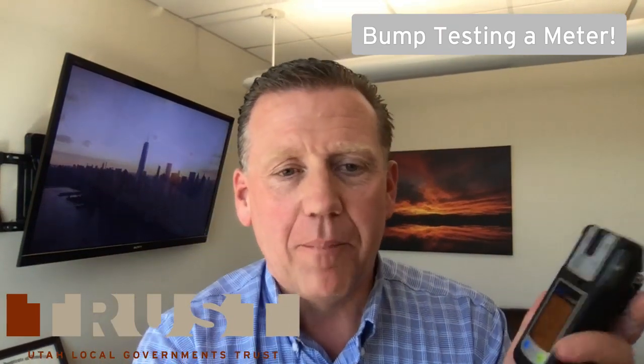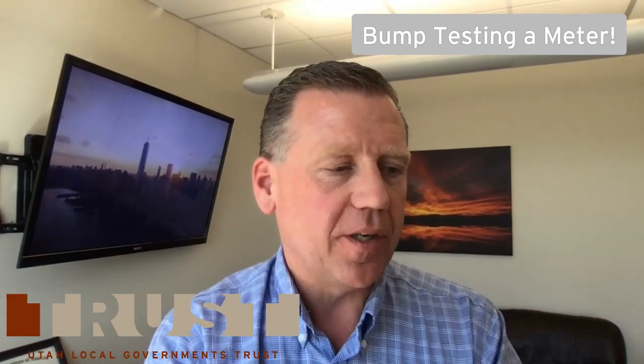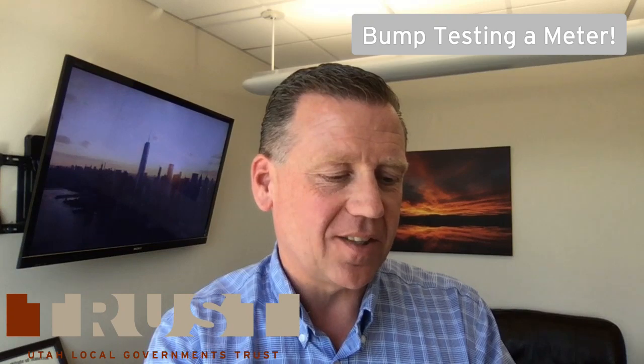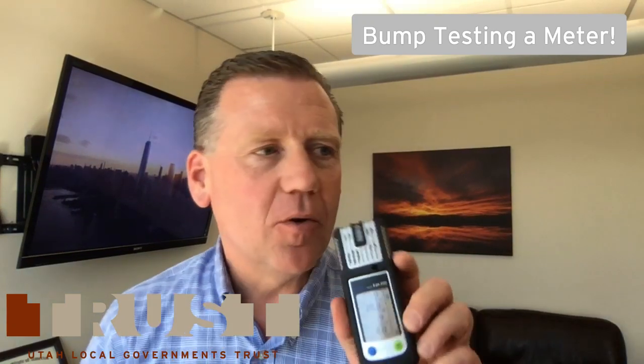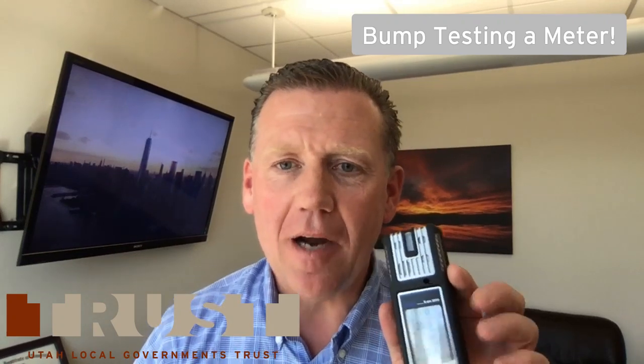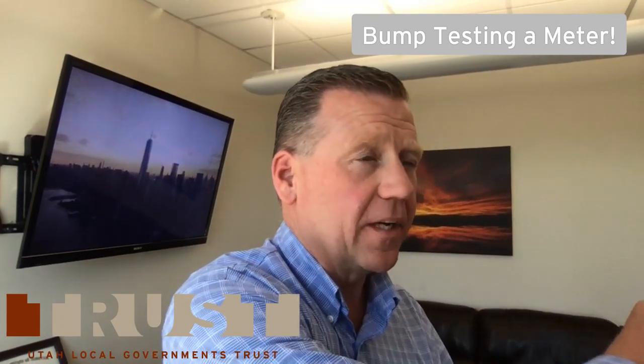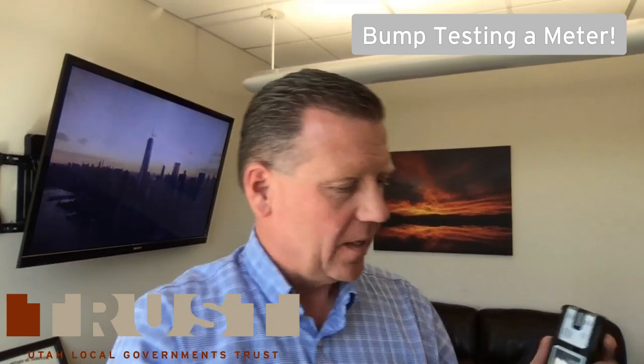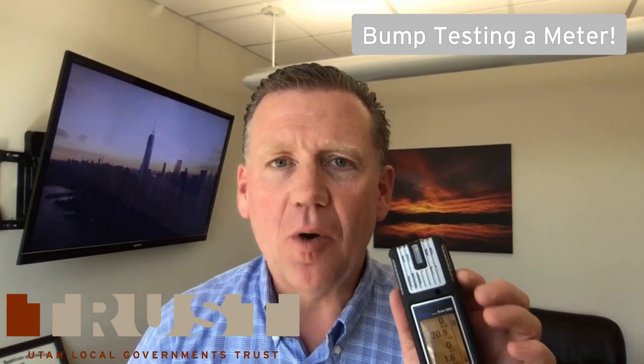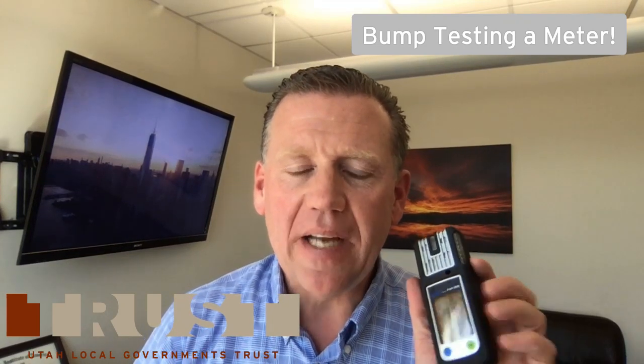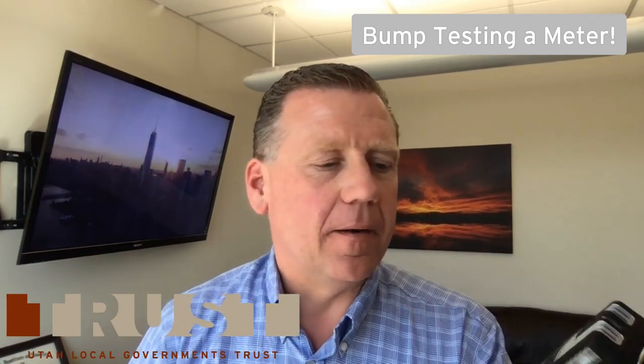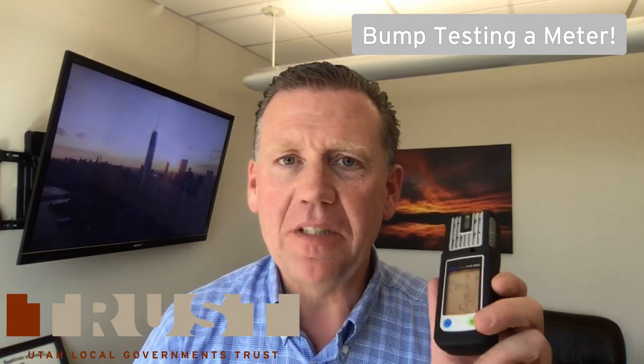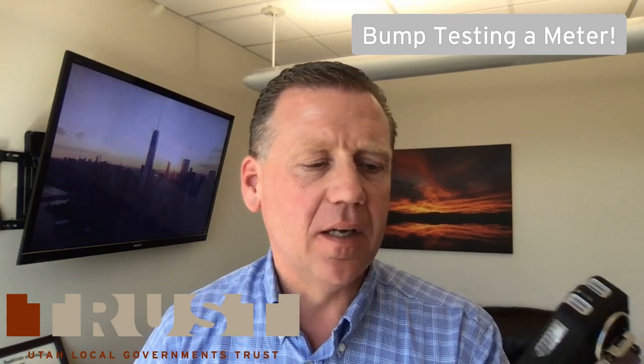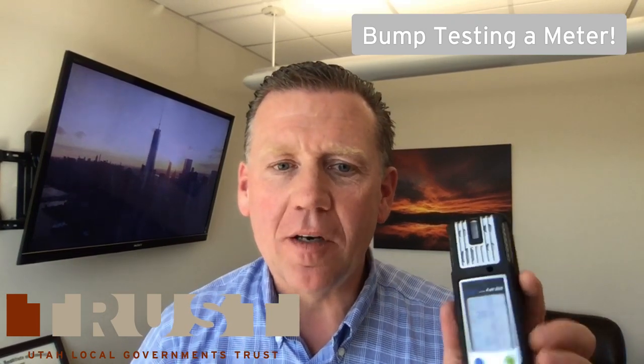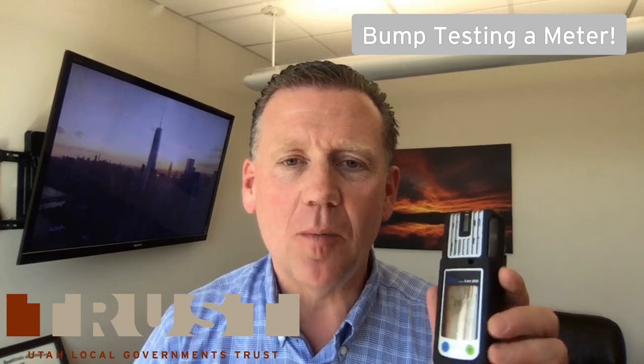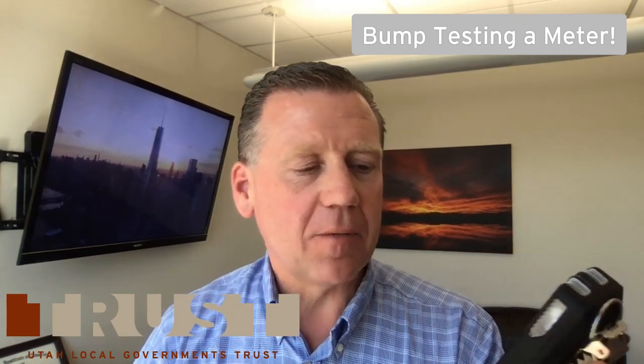Okay. Because that is out a little bit, I'm going to recalibrate that meter. I'm sorry, guys. I got that noise going on. I'm going to recalibrate this meter because I'm not reading accurately. Don't forget to turn off your gas. And I'm going to take it through the process to recalibrate it. If it reads exactly right, I'm good to go. Within some minor tolerances. If I'm tenths out, or like I said, within 1 part per million on carbon monoxide, and it's kind of bouncing around that number, then I'm going to be okay there.